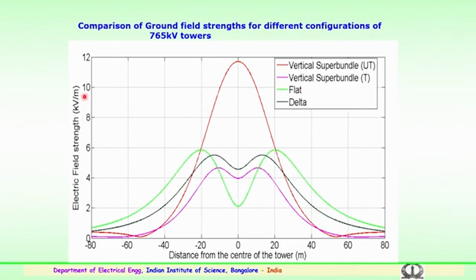Here you can see the electric field in kV per meter versus the distance from the center of the tower. Very clearly you can see when the line is transposed, when the conductors are transposed, the levels of electric field stress reduce. This is again in case of delta, the pink color shows the vertical super bundle, whereas for untransposed you can see that the electric field strength is very high, near 11 or 12 kV per meter. For the same tower with the transposition it comes down to 4. So, it reduces to 1/3 of the value. So, the very clear conclusion is that going in for transposition will be the better option for reducing the electric fields.